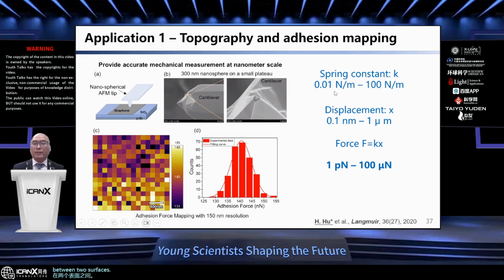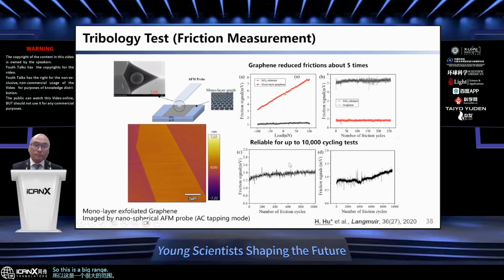If we do a quick calculation, we can design the spring constant of the micro cantilever from 0.01 Newton per meter to 100 Newton per meter. If we can detect the displacement in the vertical axis from 0.1 nanometer to 1 micron, we can achieve a force range from 1 piconewton to about 100 micronewton. So this is a big range for measurement.